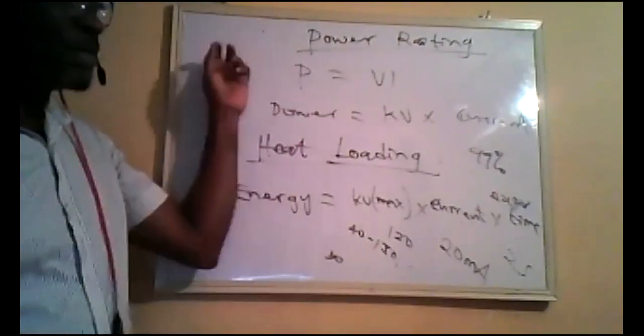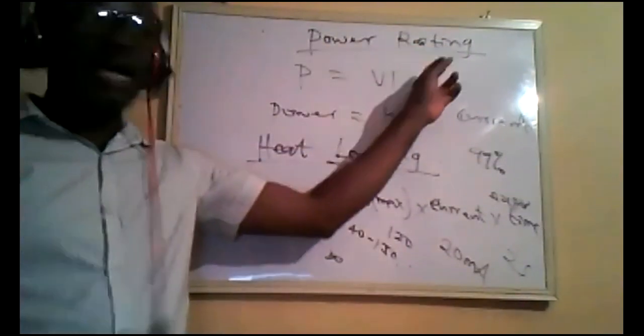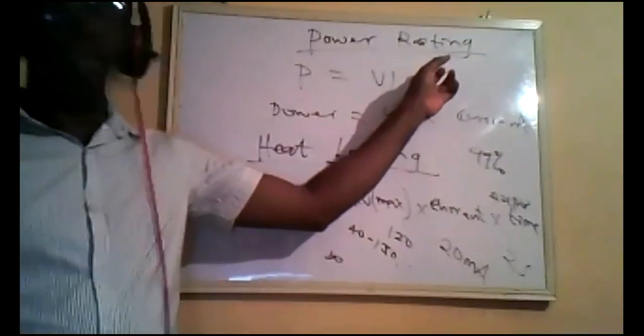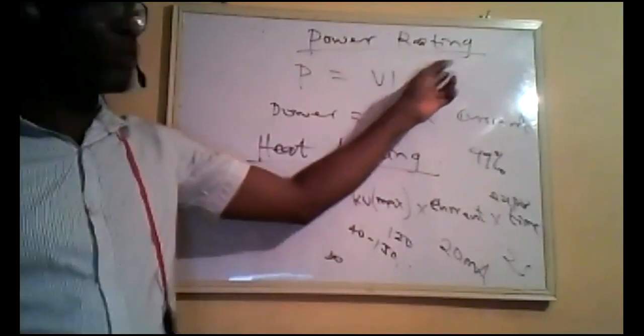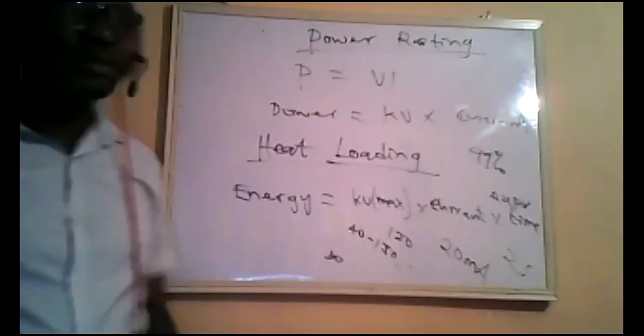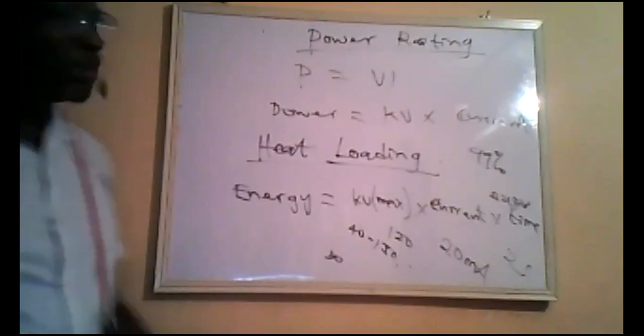For that particular machine, the C-arm fluoroscopy, it is mobile and uses a stationary anode. Because of that, we can't use it for an extended period of time. We just use it for a very short period of time, put it off again, and use it for a very short period again.